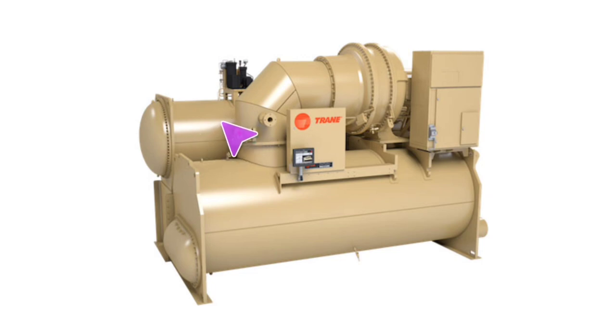The most common way that ends up happening is usually on the condenser water side. We either lose GPM or end up running too high of condenser water, whether it be something going on with the towers or the fans or something that causes too high a temperature on the condenser water. On low pressure machines, which right now is primarily just your Trane equipment, the atmosphere in the system does also play a heavy role in surge a lot of times. That's kind of a third factor but not a part of this conversation.